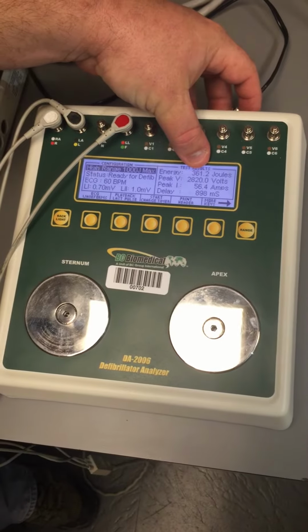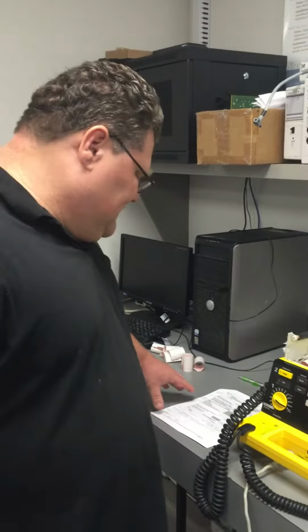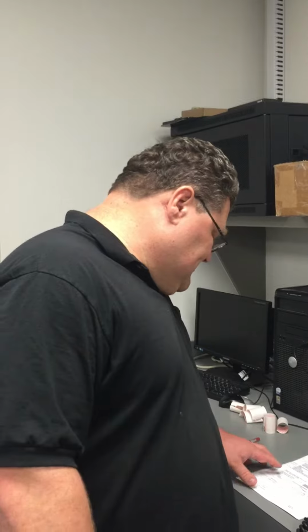It took 4 seconds to charge to maximum energy and gave us an output of 361.2 joules, which means the device is very accurate and very fast. It's given up to 15 seconds to charge, and the error output is given 15%. Our error was less than 1%, which is actually a very nice machine. Is it 15% in either direction? Yes. Okay. 15 up or down.